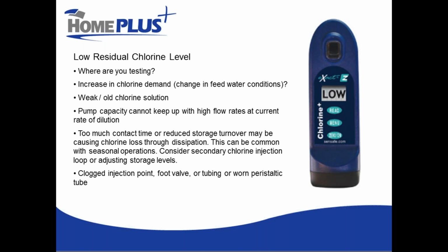Sometimes though, you end up with a scenario where your pump just cannot keep up. So it's pumping literally as fast as it can, but in between signals that it's getting from your water meter, it can't complete the dose of chlorine before the next signal to inject more comes. So sometimes you can fix this problem by reducing your rate of dilution. You literally have to inject a stronger solution to get up to the level that you need to.